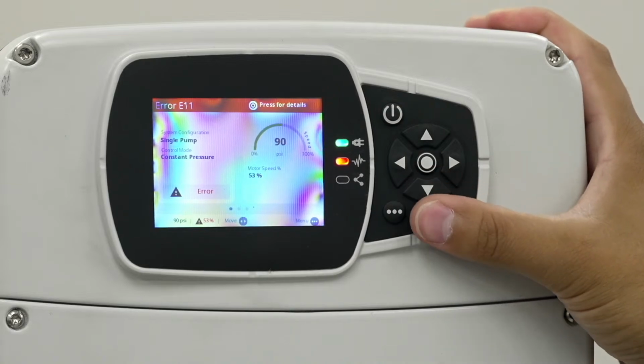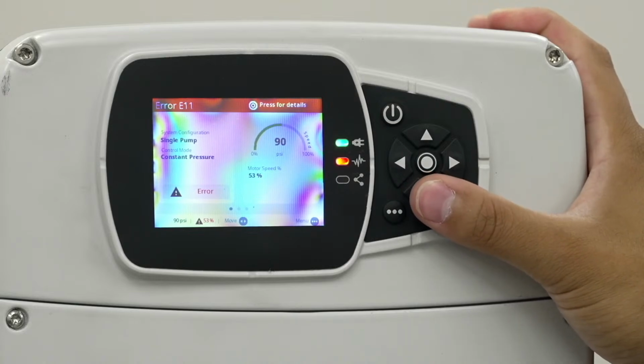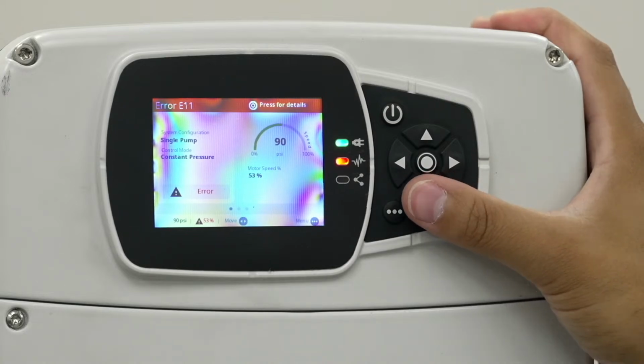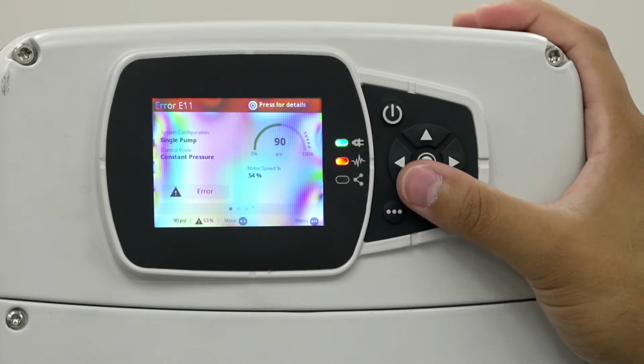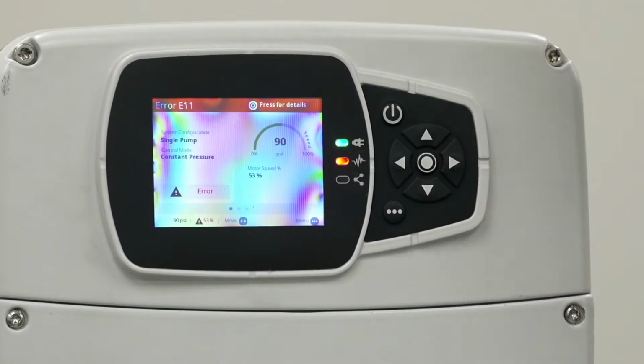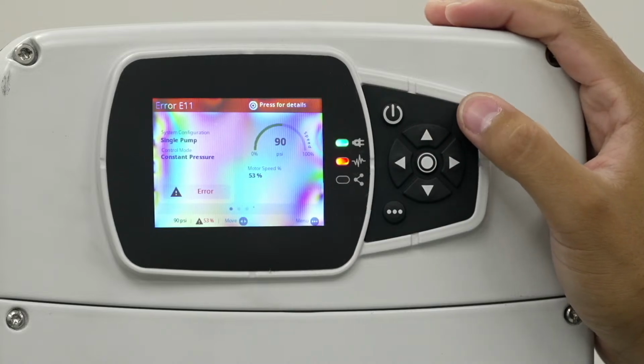Long pressing the down button: we don't have a multi-pump system right now that's truly activating, but this is going to force alternate. You're always going to have a lead pump in a multi-pump application. By long pressing this down button, it's going to force alternation and put the next pump in line as the lead pump.